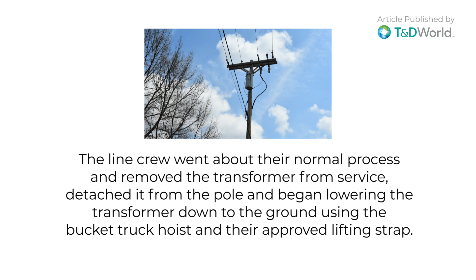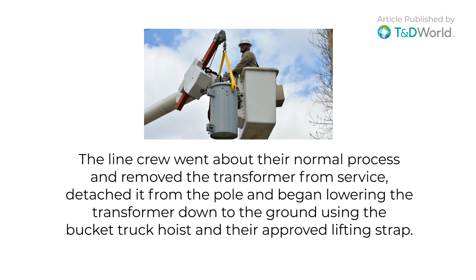So the necessary calls were made, and a few days later, a couple FIBC samples showed up. Ben said they did not have any changeouts scheduled, so their evaluation was going to have to wait for the opportunity. They did not have to wait too long. Just a week later, they were able to test this FIBC bag out. The line crew went about their normal process and removed the transformer from service, detached it from the pole, and began lowering the transformer down to the ground using the bucket truck hoist and their approved lifting strap. With the transformer placed in the waiting FIBC, the line crew then attached the hook to the woven fabric FIBC's bag straps and proceeded to lift the transformer per the manufacturer's directions.